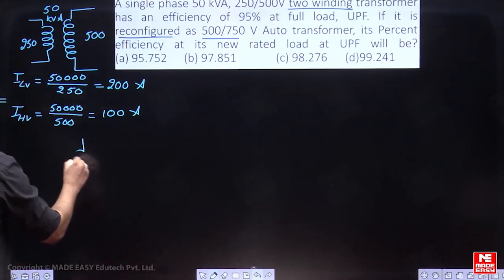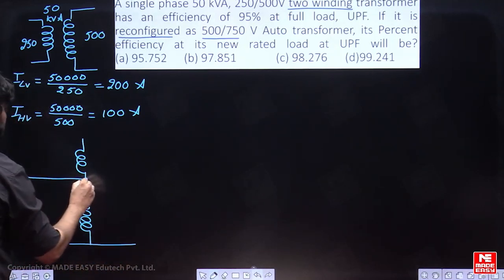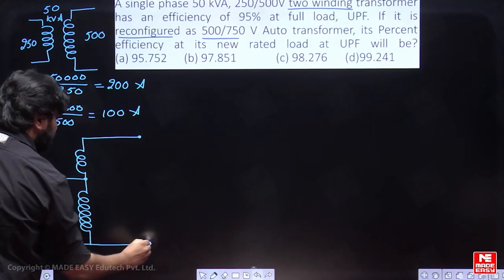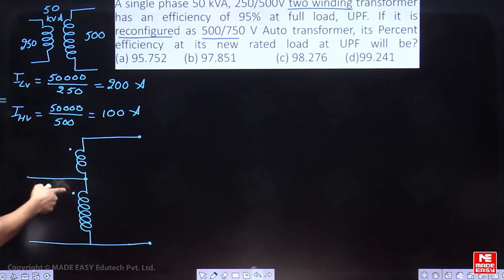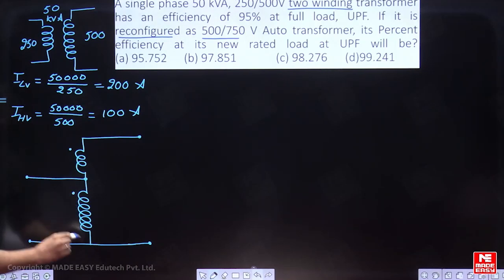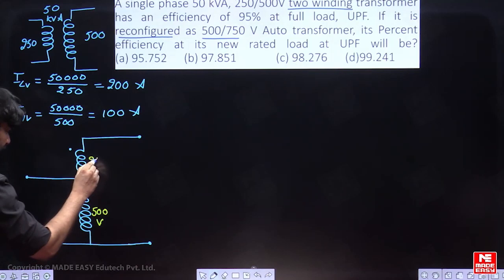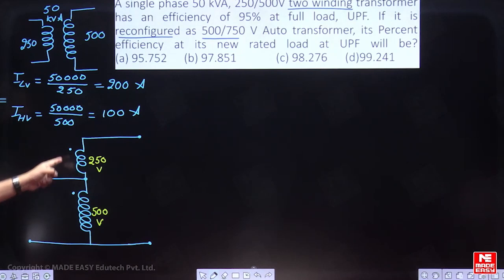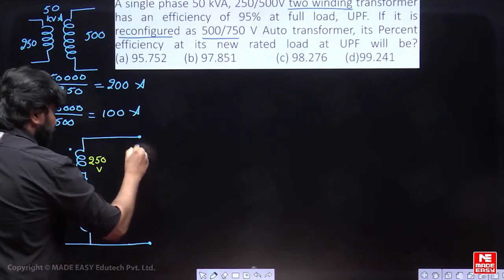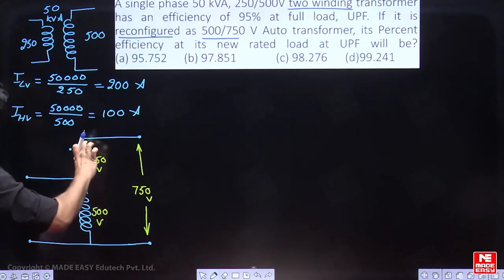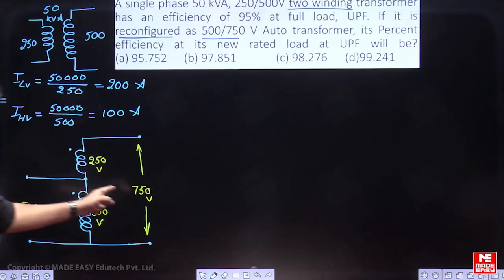I will draw so you understand easily. Taking the 500-volt winding and the 250-volt winding connected in additive polarity mode: the output voltage is 750 volts, and the input is 500 volts. The common winding is 500 volts; 500 plus 250 in additive polarity gives 750. This is now a 500 by 750 volt auto transformer.